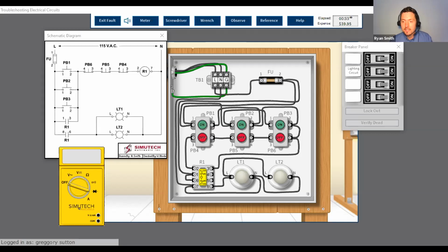Let's see. Can you demonstrate a Megger test? We can, and we do in the classroom. Unfortunately, we don't have time on this webinar, but we have a simulated Megger test where we have 4 different motors. Each gives different readings that seem good at the time on the regular resistance, but when you do the megohm resistance, something's not quite right. So yes, that is available. Unfortunately, we can't jump into it and download it right now, but it's out there for sure.